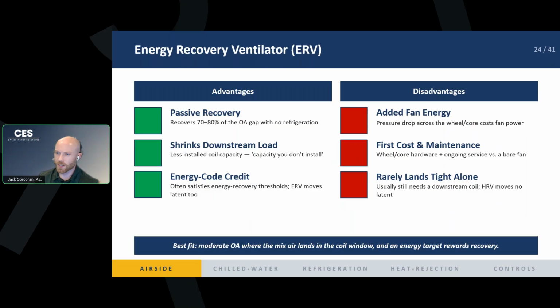And what about our ERVs, right? So some advantages of this, you get free energy, right? You get to recover up to 70 to 80% of that energy from our return air transfers into the outside air, and it allows us to downsize the coil downstream. So that's that second point. If you can lower that 95-degree temp air to 81, that's a significant change in your coil size and you get a lot of cost savings, right? That free energy is great to reuse here.